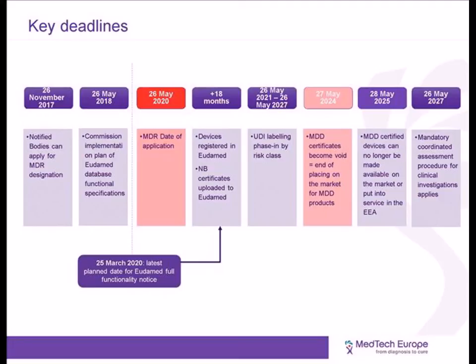In any case, 27th of May 2025 is the final date on which any medical device certified under the previous directives may be supplied within the European Economic Area or made available to the final user. There is no obligation to recall devices which have already been supplied before this date, but after 27th of May 2025, effectively all devices made available in Europe must be EU MDR compliant.